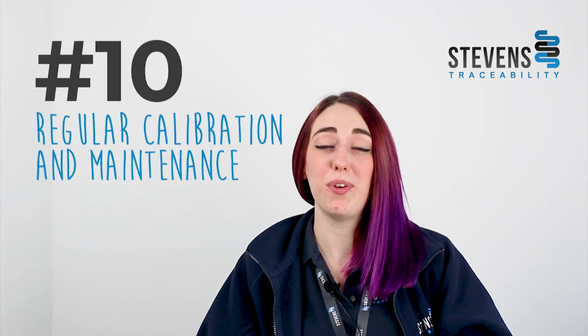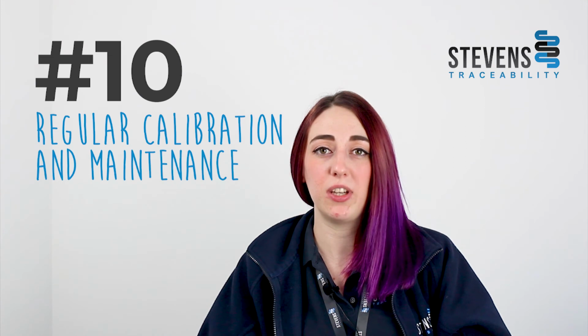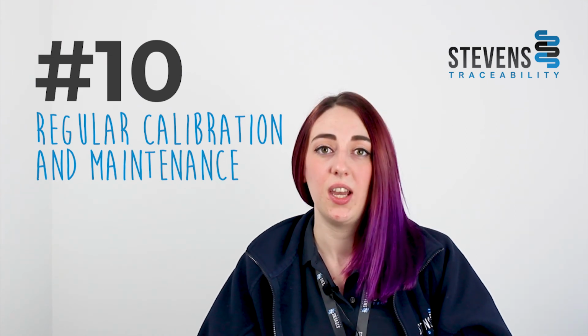And my final tip, number 10, is to have regular calibrations and maintenance visits. The amazing difference you can have with having more than 1 visit per year, whether it's 2 calibration visits, or 1 calibration and 1 maintenance visit, is insane. You can have instant checks 6 months in to see if there are any issues that could occur with your weighing machine that you wouldn't notice later on. If you come once a year to calibrate a machine, it will keep it more accurate than if you never have the machine calibrated.